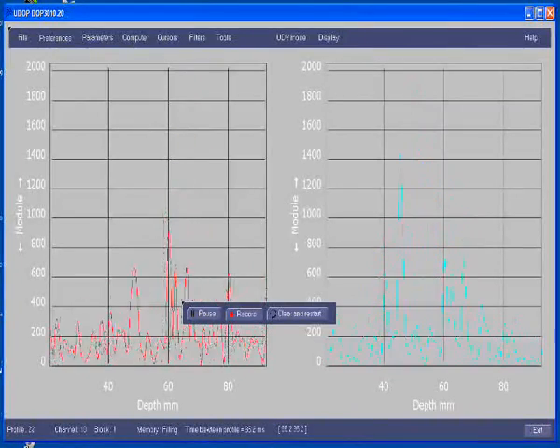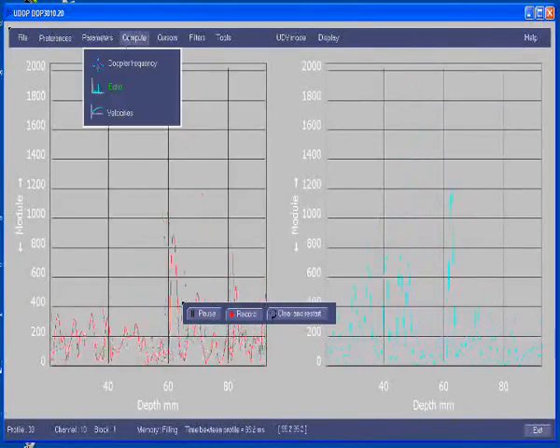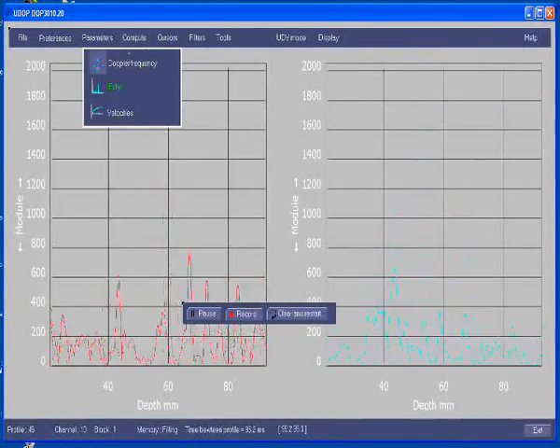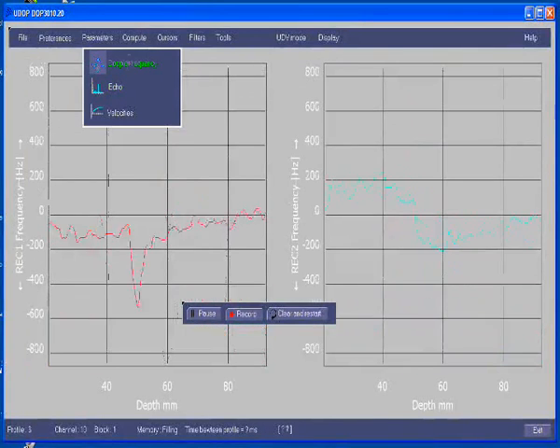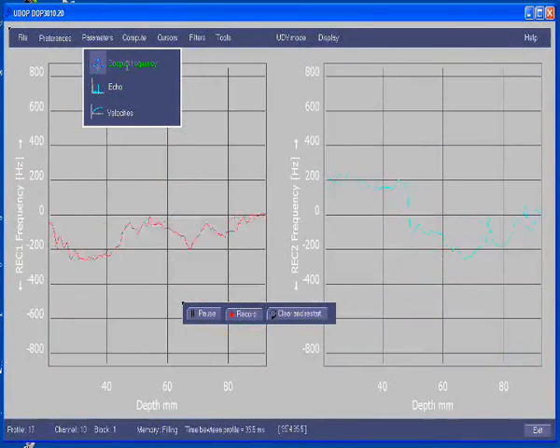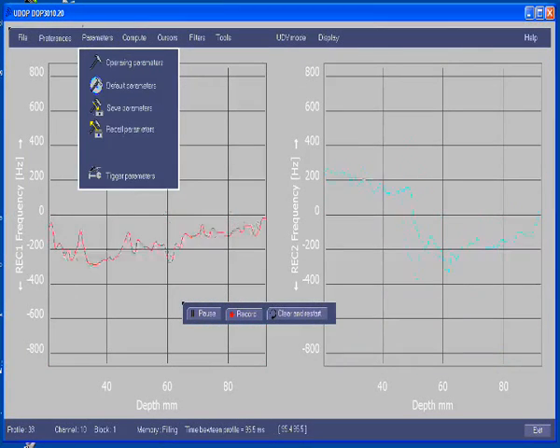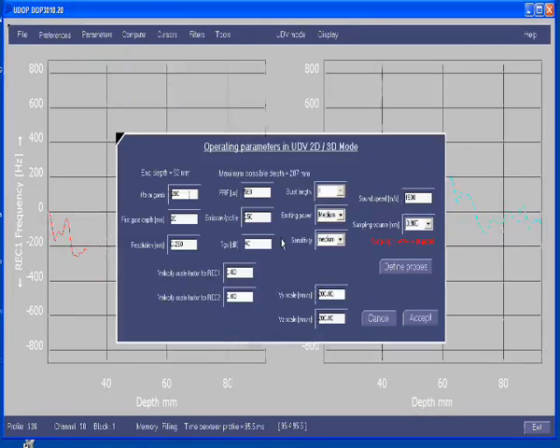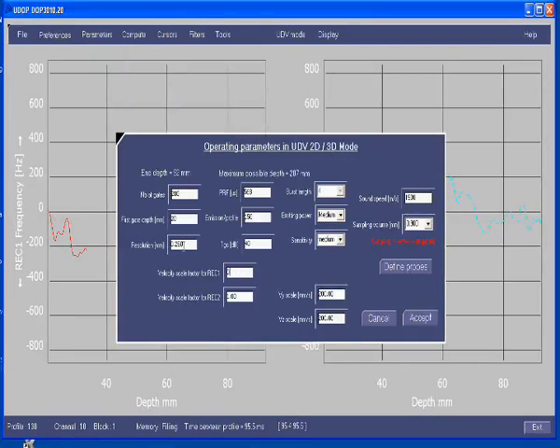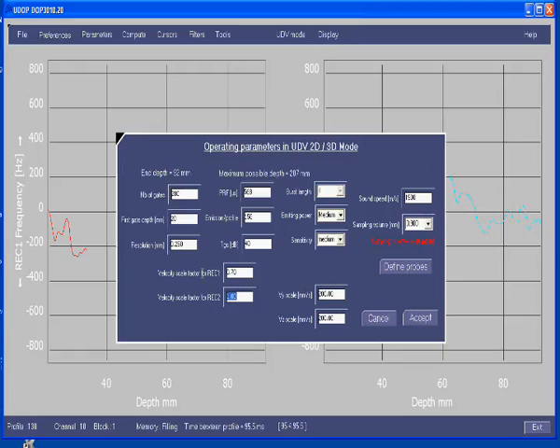As we have correct echo profiles, we can have a look on the Doppler frequencies issued from both receivers. As they do not cover the full range, we will improve the Doppler frequency scales. Let's apply a value of 0.7 to both velocity scale factors. Such a value improves the quality of the results.